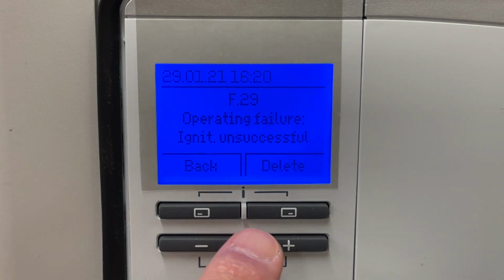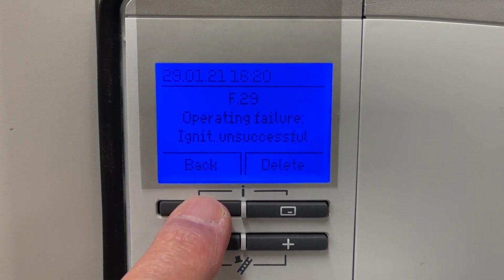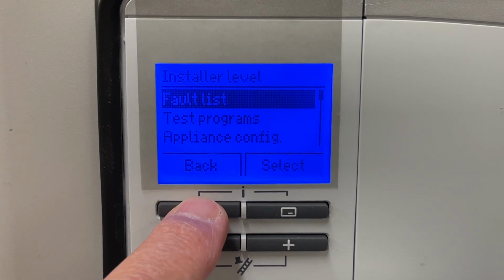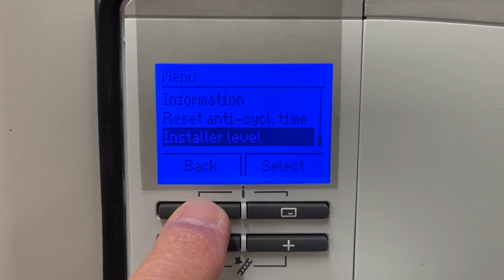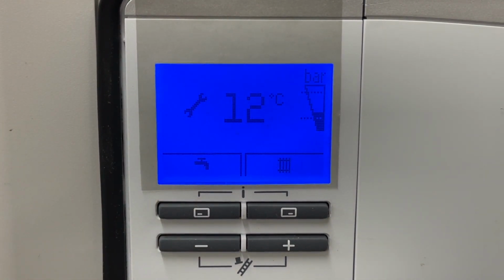Now, if you press delete, you will wipe out all of the error codes that were there. So please make sure that you write them down. But otherwise, if we go back, there'll be the fault codes list, and we can keep going back, installer level, and then back to the beginning, and those codes will still be in the memory, so the next person who comes along can see what was done before, and then repair the boiler as necessary.